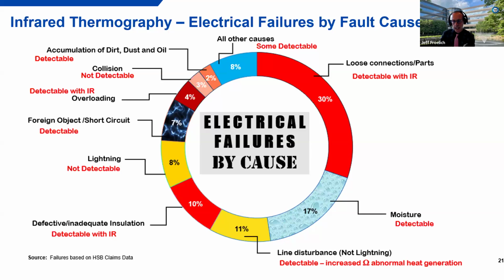Historically, as I mentioned earlier, loose connections, also known as high resistance connections, are the most significant frequency item, and it's detectable with infrared. It's shown on average aggregate around 30%. It's typically a lot higher, but aggregate-wise around the globe, different occupancies and operations will have a different percentage.